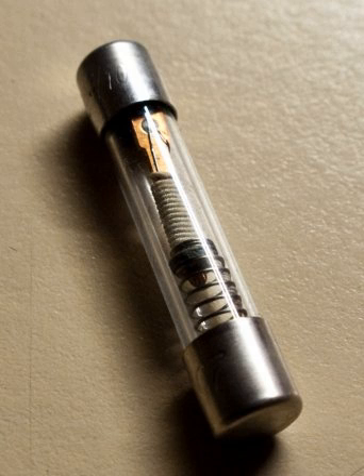Topic: Special features. Glass cartridge and plug fuses allow direct inspection of the fusible element. Other fuses have other indication methods, including: indicating pin or striker pin, which extends out of the fuse cap when the element is blown; indicating disc, a colored disc flush mounted in the end cap of the fuse, which falls out when the element is blown; element window, a small window built into the fuse body to provide visual indication of a blown element; and external trip indicator, similar in function to a striker pin, but can be externally attached using clips to a compatible fuse.